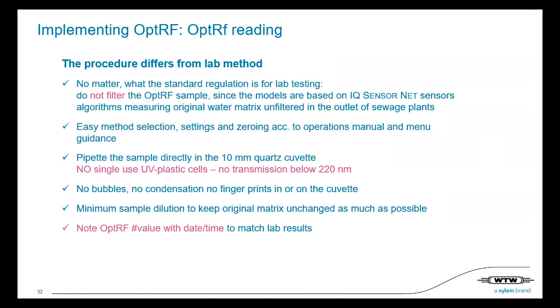A very important part is to pipette the sample directly into a 10 millimeter quartz cuvette — a quartz cuvette, not a UV plastic cell. They start with transmission not below 220 nanometers, and we start our scan at 200, so it must be a quartz cuvette. No bubbles, no condensation, no fingerprints, no scratches, no dirt.